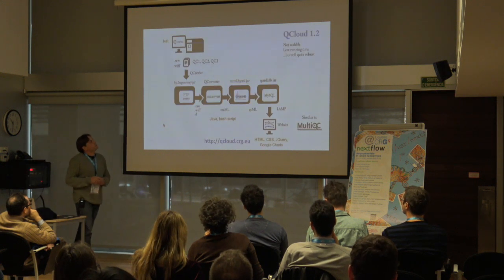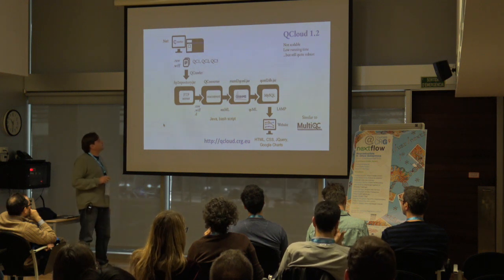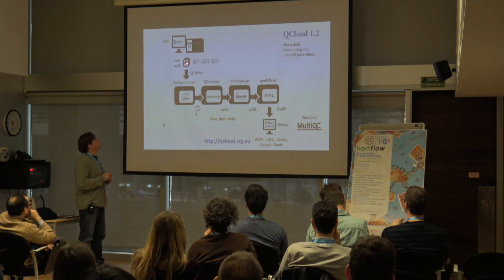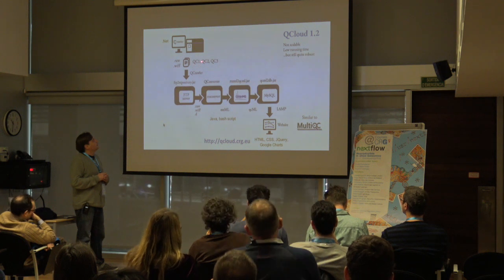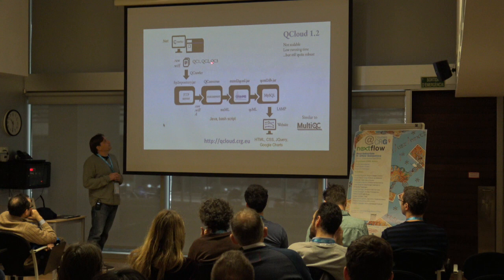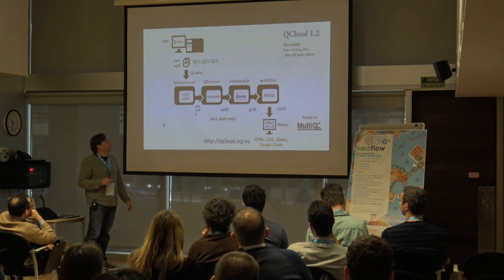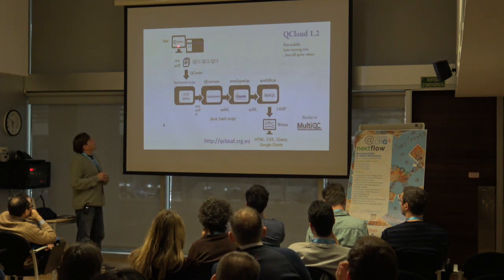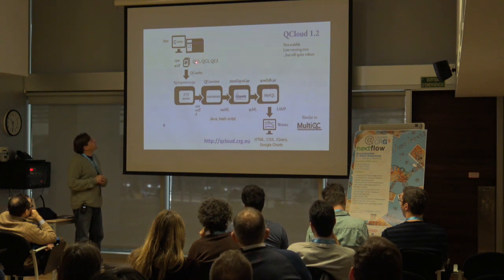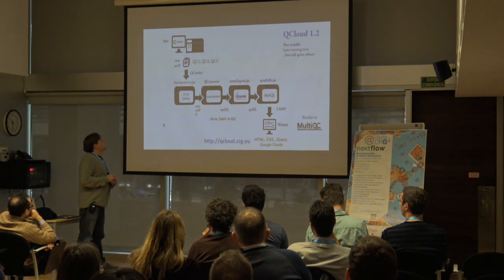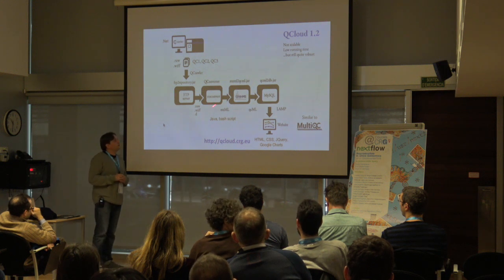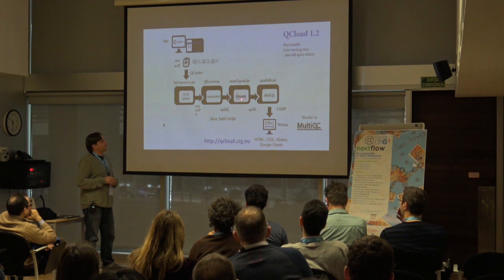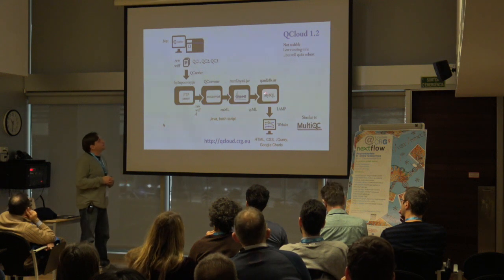So for that we created Q-Cloud. The idea is very simple from the point of view of the mass spectrometer operator. The operator only has to inject specific quality control samples: QC1, which is a low complexity sample; QC2, a more complex sample; and QC3, which is also more complex but with some specific peptides. We created a small client called the QCrawler, which sends the data acquired from these QC files to our servers at the CRG. Here we convert this data to MZML, which is an open format for proteomics data, and analyze it with OpenMS — open mass spectrometry software that allows us to extract all the quality control data from the file.